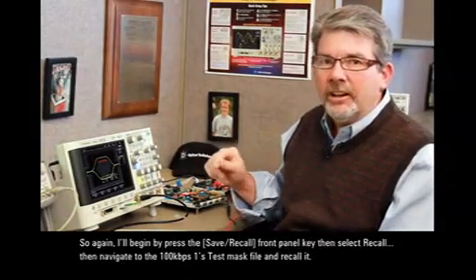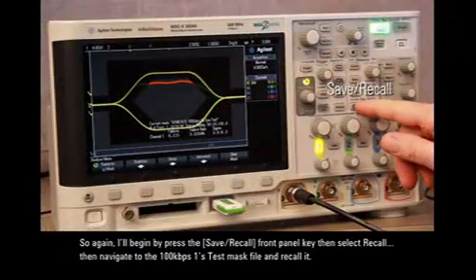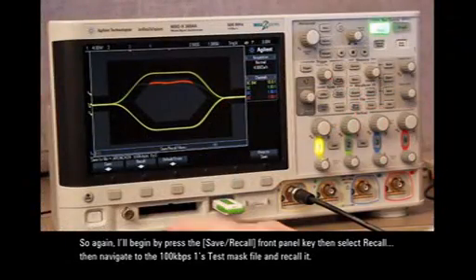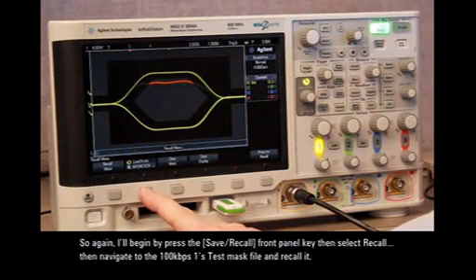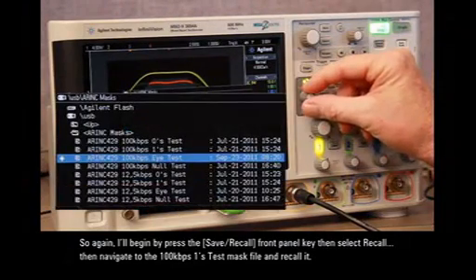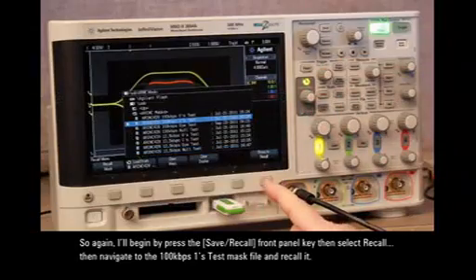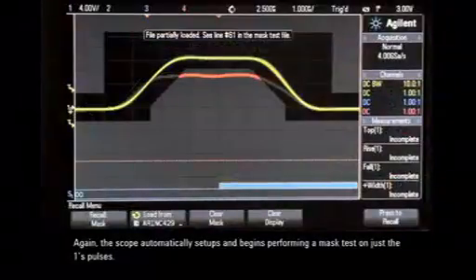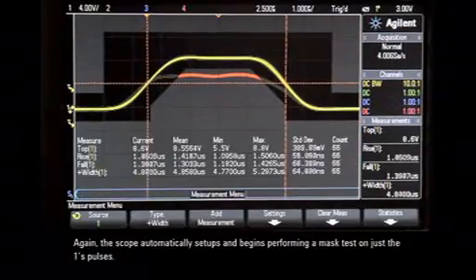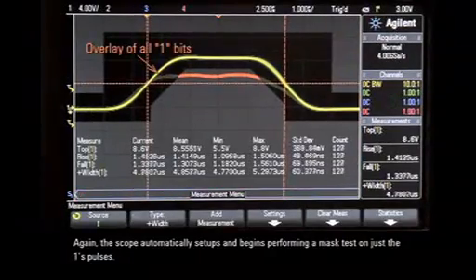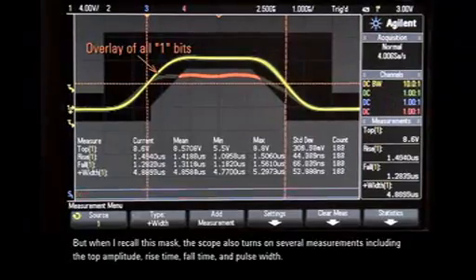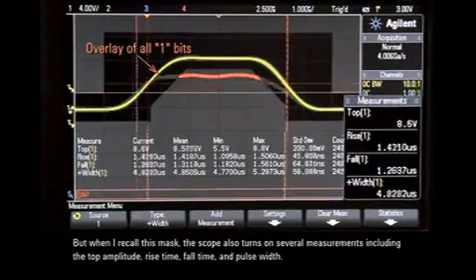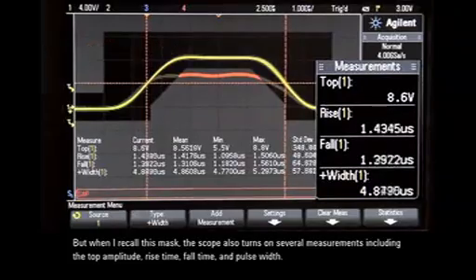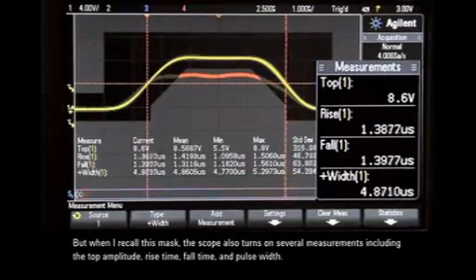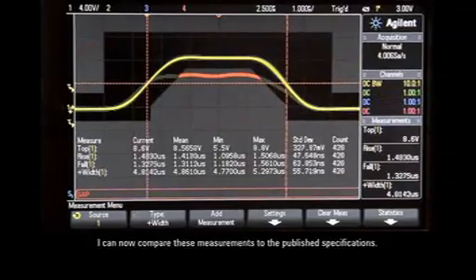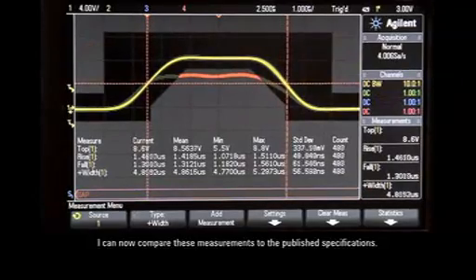So again, I'll begin by pressing the Save/Recall front panel key, then select Recall, then navigate to the 100 kilobit per second ones test mask file and recall it. Again, the scope automatically sets up and begins performing a mask test on just the ones pulses. But when I recall this mask, the scope also turns on several measurements including the top amplitude, rise time, fall time, and pulse width. I can now compare these measurements to the published specifications.